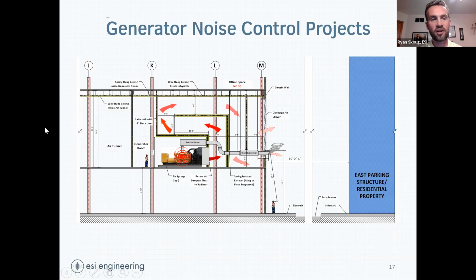They gave us this whole tunnel all the way through the building that we were going to pull air through. So we ended up creating a labyrinth path with a wall, then a wall coming down from the ceiling, then another wall, so the sound had to go up and down to get through the tunnel and block noise. I engineered this labyrinth where the sound had to come back over the top of the generator and out and around.